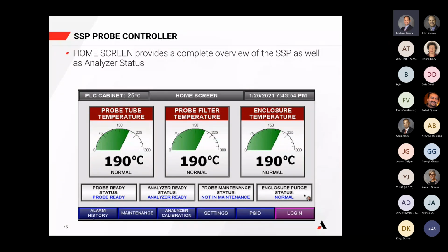And it even monitors whether or not the purge is working properly. So again, if the purge goes out, we would expect to see that the users need to shut down the system because they could be violating some requirements of their hazardous area certifications. So from this screen and on many of the subsequent screens, and I'm trying to get an animation to work here. Rod, I don't know if you can advance us here. You'll see right down here, we've got a full bar of, I guess, destinations would be the best way to put it, so that we can move off of this home screen and view some other aspect of the analyzer system, this SSP system, and see how things are operating.